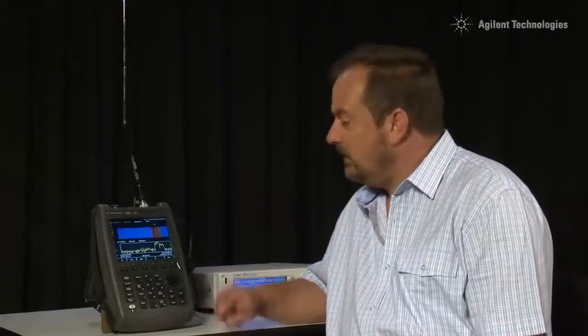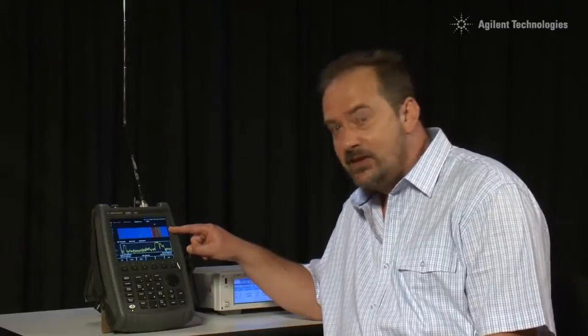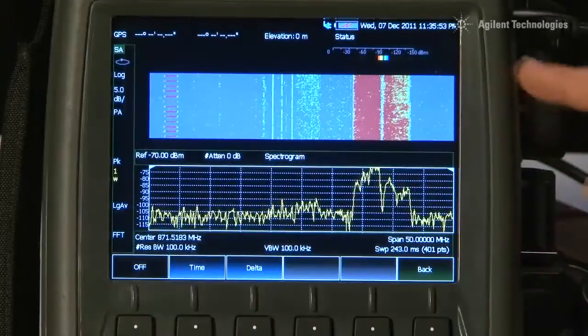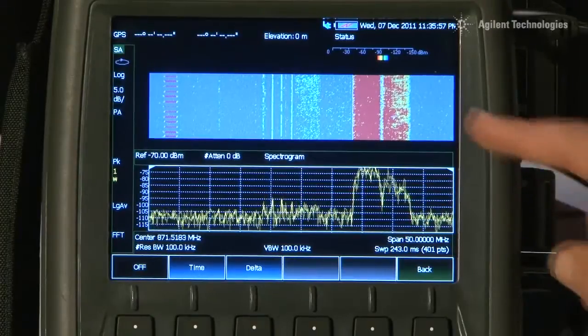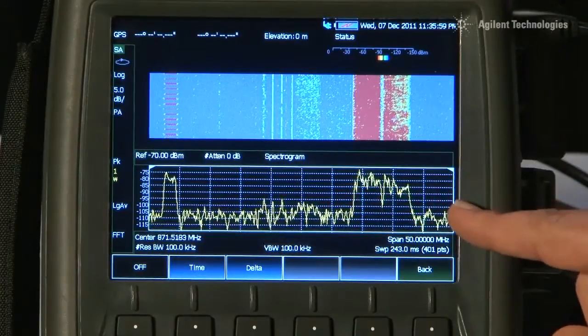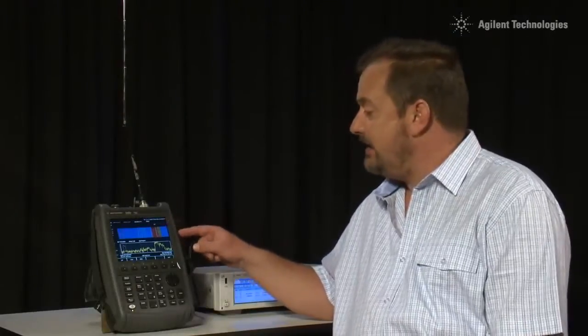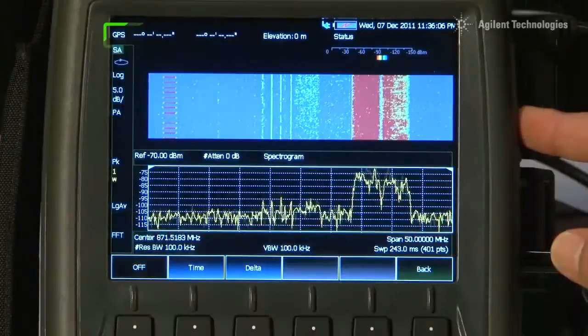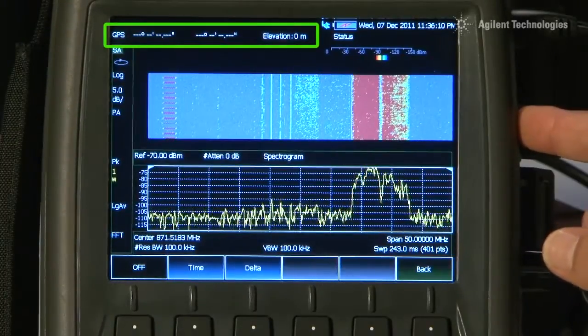And best of all, every captured trace can be logged and recorded into either the FieldFox's internal memory or onto a USB memory stick or the mini SD card. And as well as storing the frequency and amplitude data, it also stores the date and the time, and if we have a GPS receiver plugged in, it will even store the lat and long position of where that trace was captured.